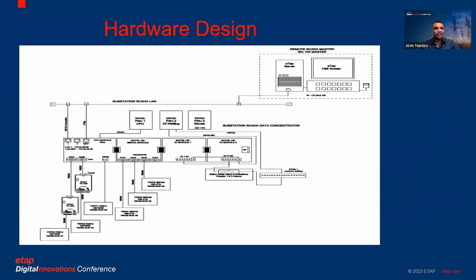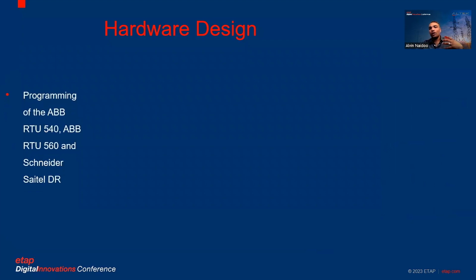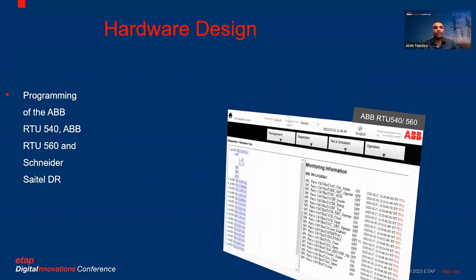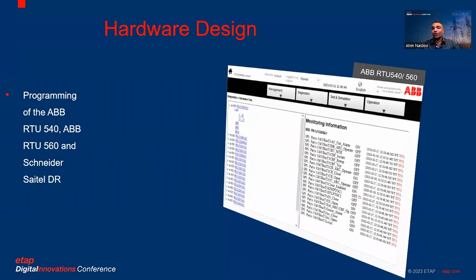Here's some of our design work that we undertook. As we can see, there's multiple converters that we've got along the way for your Modbus and serial communication, utilizing your 485 to 232 converters and so forth. So programming of these particular RTUs, we had 3 RTUs that we used in the system throughout the network. At each substation, these 3 types of RTUs was the ABB RTU 540, where we programmed accordingly for the various signals that we did bring into the system. We had the Schneider Saitel DR RTU as well.